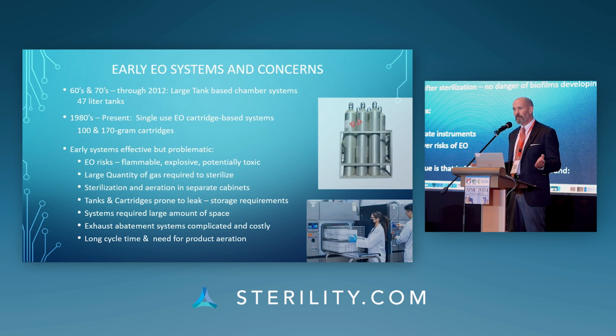But the problem with both of these systems was pretty much the same. Both the tanks and the cartridges leaked. They had to be maintained in special ventilated storage areas. These systems required a fairly large amount of gas to sterilize. Sterilization and aeration took place in different cabinets, so someone had to move product from the sterilizer to a separate aeration cabinet, and this provided the potential for exposure during the transfer of product.